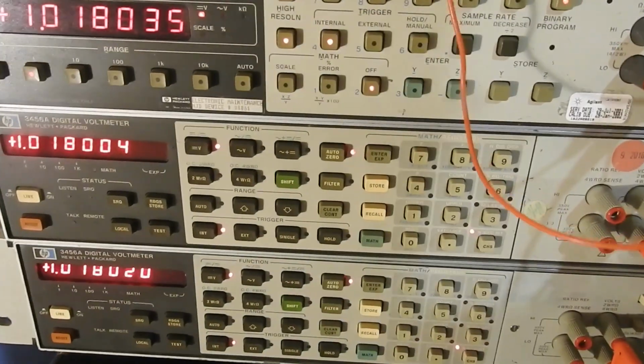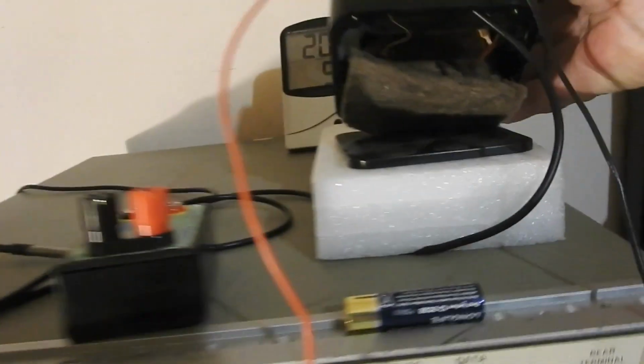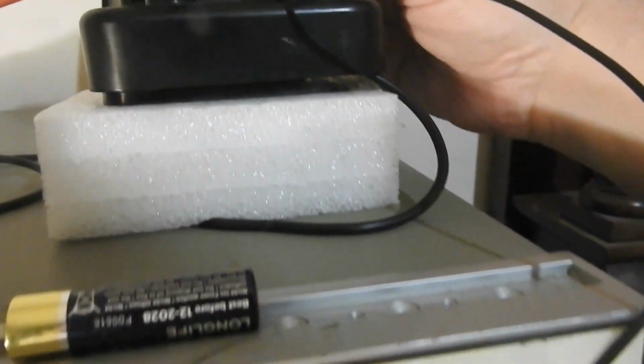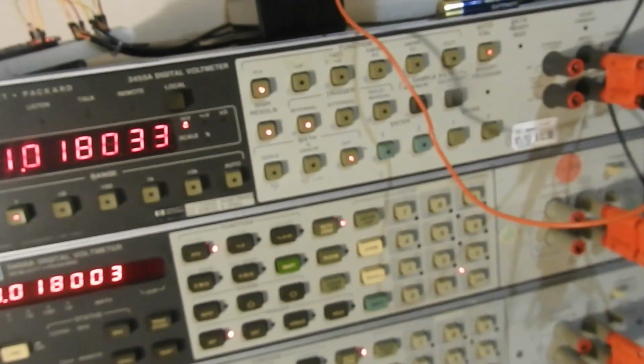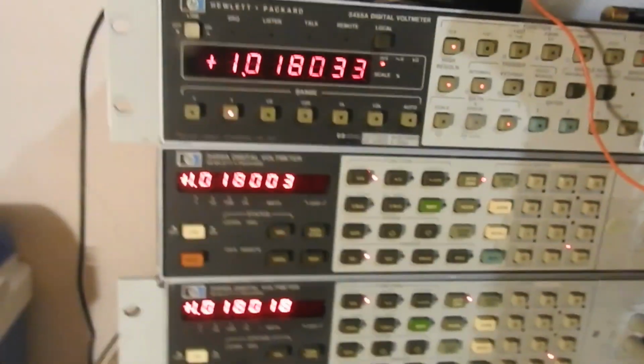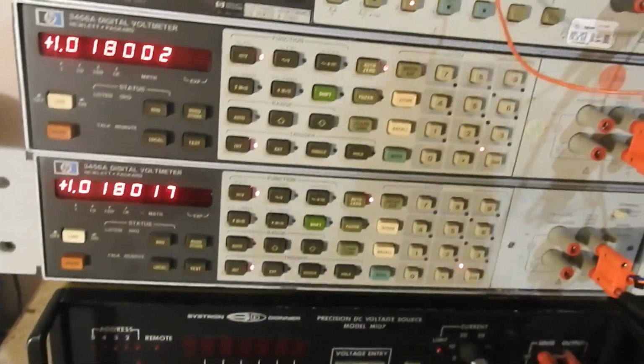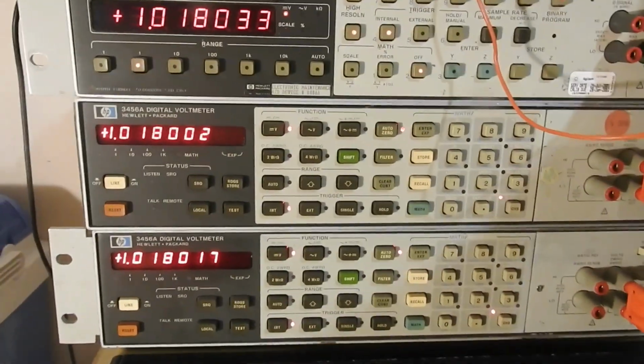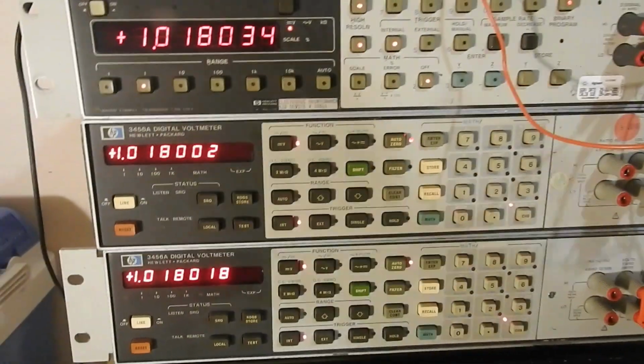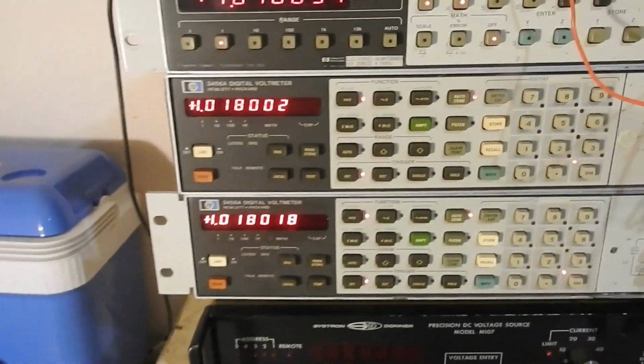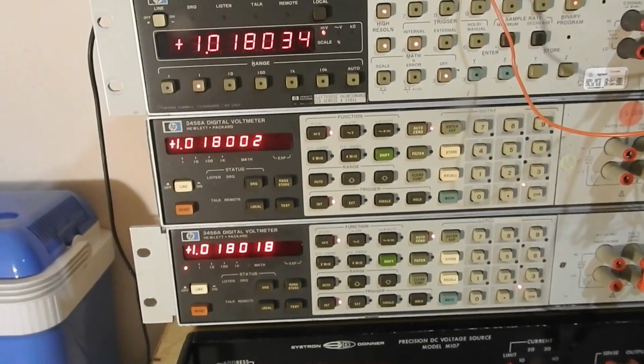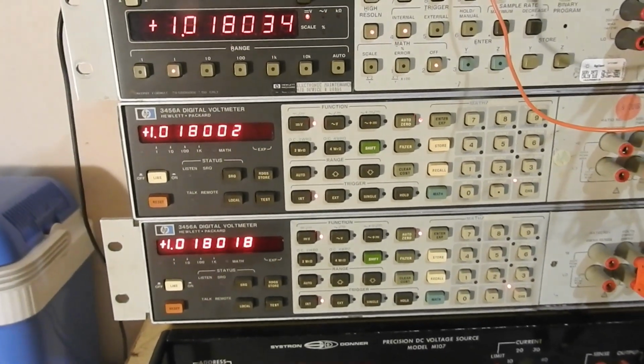Now these guys can take, whoops, you can see a bit underneath there, there's a cell falling out. I don't want to disturb it too much. You've got to keep them vertical as much as possible. These can cope with being on their side or upside down. There's another sort. These are unsaturated Weston cells. Saturated Weston cells cannot be turned upside down. They'll be ruined immediately. They're more for fixed laboratory standard use.